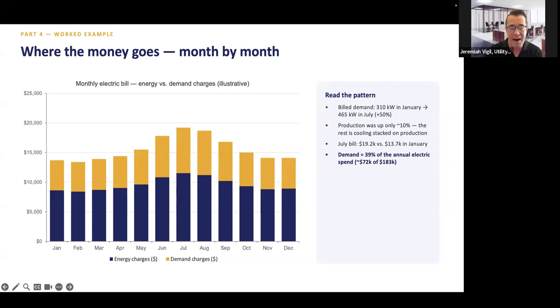But what's always higher, especially in printing presses and manufacturing sites, is the demand. The gold is the demand, which is always higher. Billed demand is 310 kW in January compared to 465 in July in this pattern - almost a 50% increase. The takeaway here is it's about a 30 to 70% range that's never really talked about.